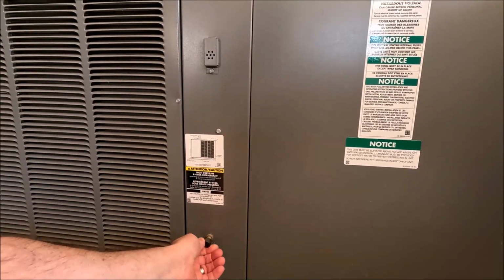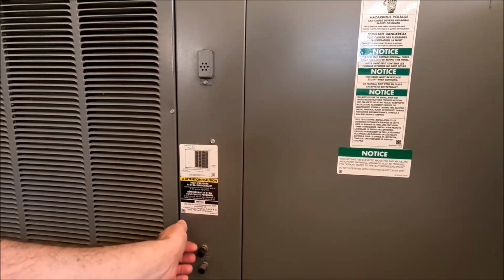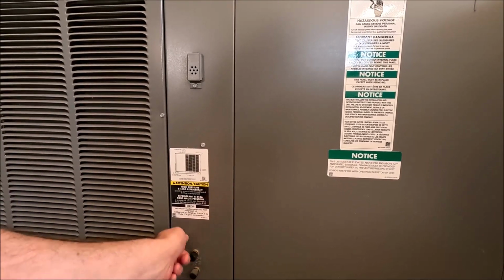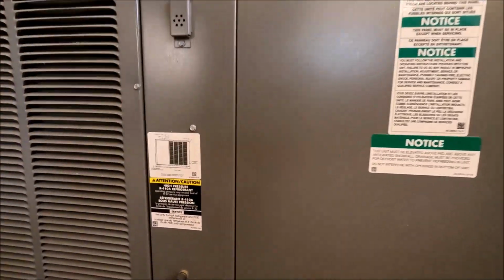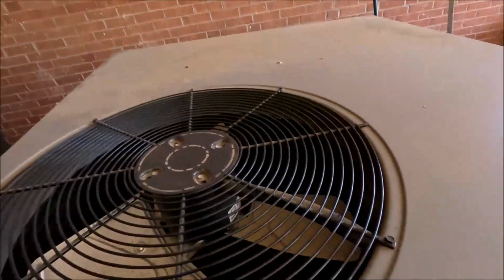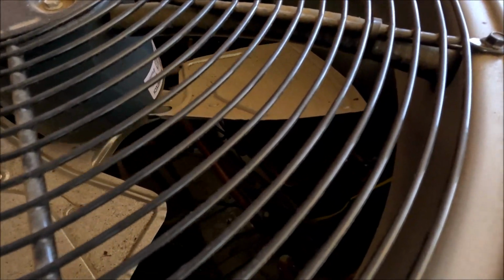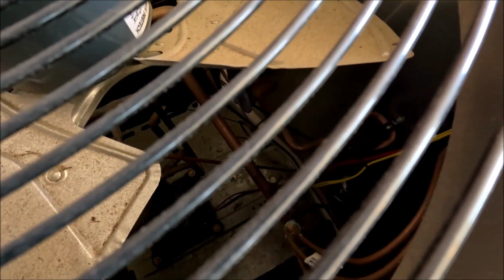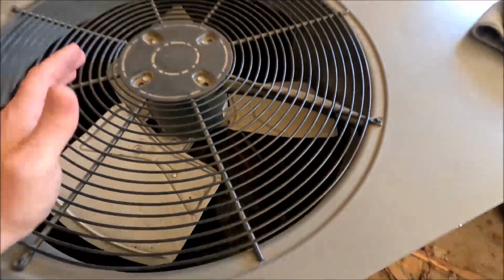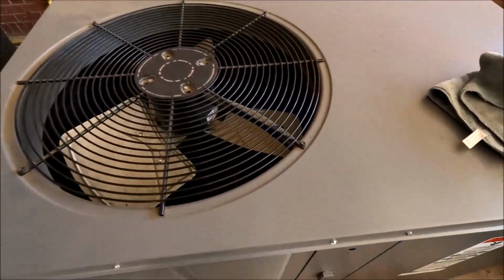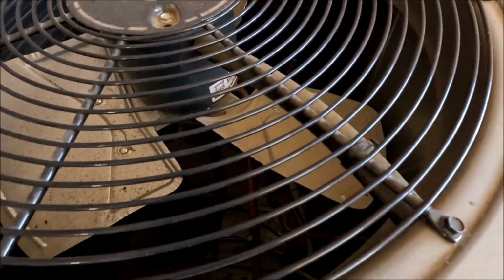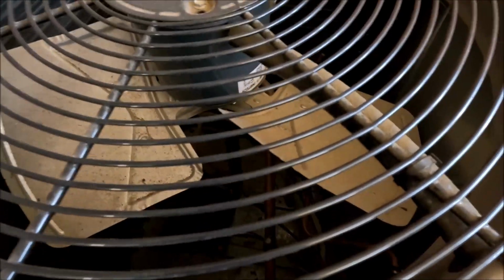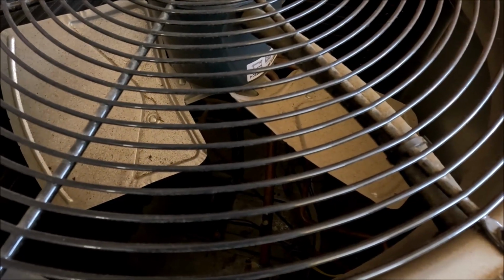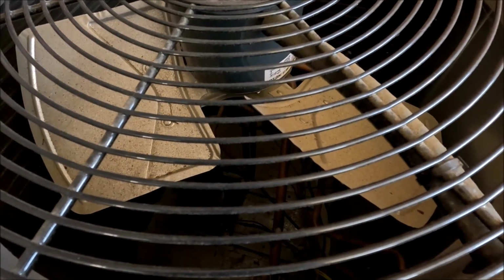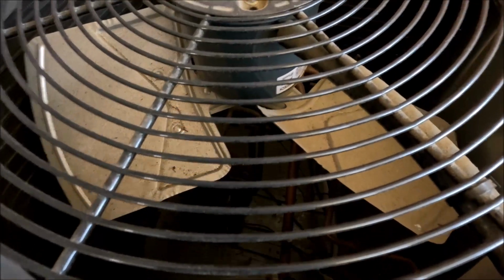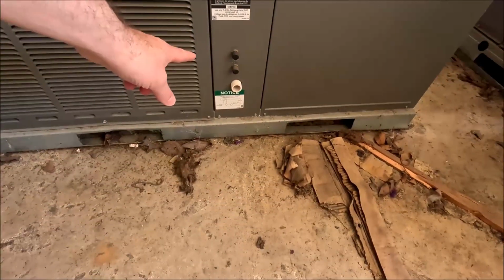The one on top is the high one because it's higher, and the one on the bottom is the low. So you can have an access port on an exterior wall like that, but behind it they're just going to run a tube and connect it into the system on the low line and the high line. If it's a heat pump, it doesn't matter. They're going to find the common low and the common high side. In the case of a heat pump, that would be between the reversing valve and the compressor for the common high and the common low. So it just depends on which one you're trying to get to. But yeah, that's just another example of how it would hook up.